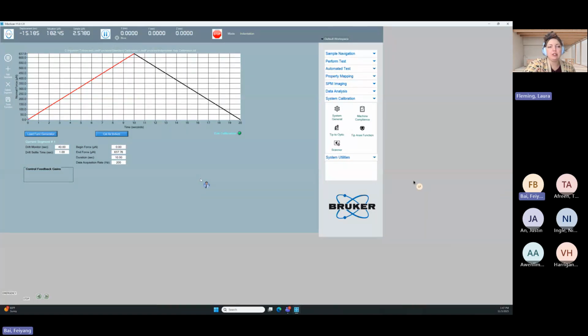What's important here is that you can see it says cal air indent, meaning a calibration air indent. I bring this up because there are other ways to do other air indents, but they don't calibrate to it. Here we are entering a specific calibration regime that we need to do daily to account for changing environmental factors. So go ahead and click cal air indent, and we're just going to actuate out and back.